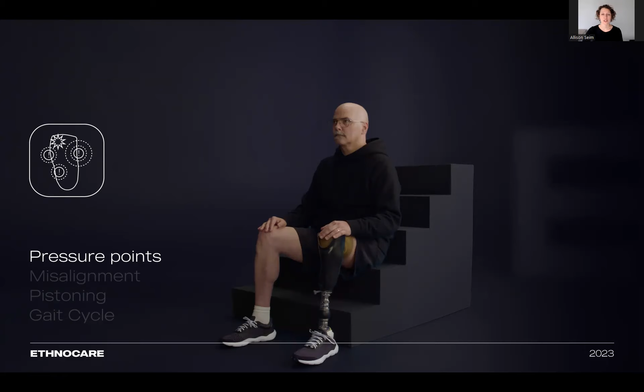So according to research, volume and shape changes in the residual limb lead to several problems and can put individuals at a higher risk of sustaining injuries. When the volume of a person's residual limb decreases, bony prominences, such as the distal anterior tibia and the head of the fibula, are subjected to increased stress, which can cause pain and elevate the risk of injury. The variation affects the pressure and distribution of shear stresses within the socket. Due to the changing volume, the alignment and anatomical support points within the socket will shift, which can result in increased pressure and shear forces. These factors can lead to problems with socket adaptation, instability, and potential skin breakdown.